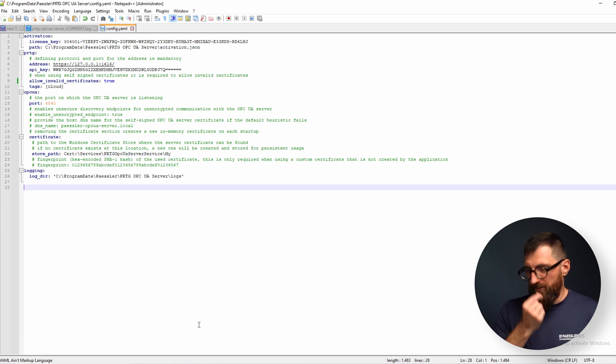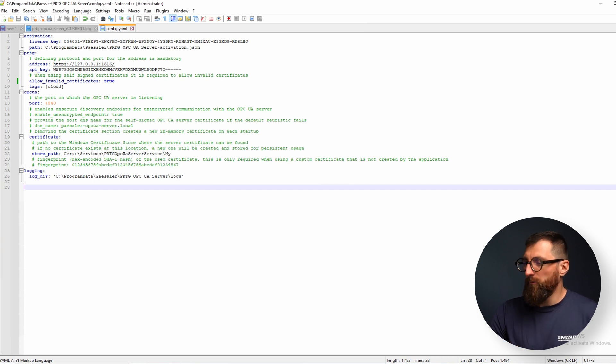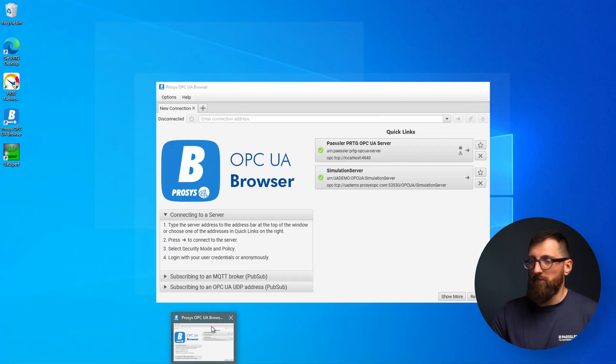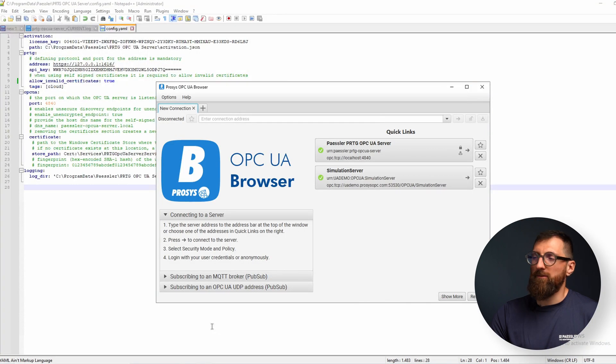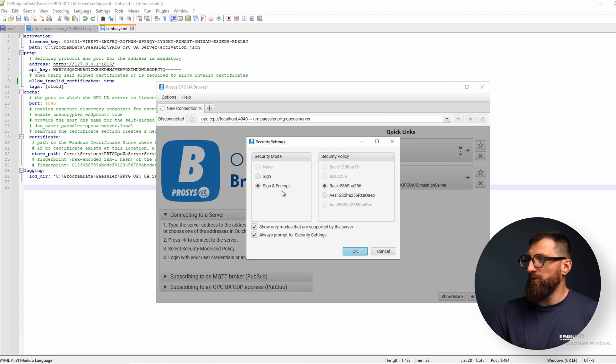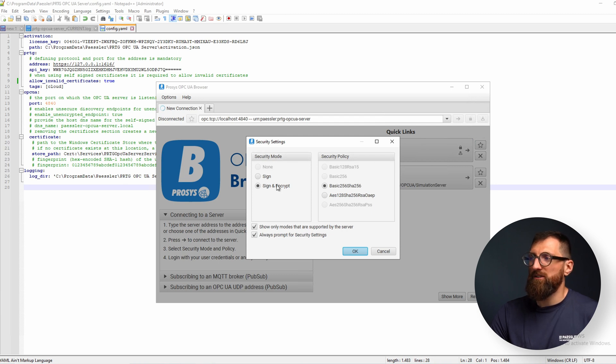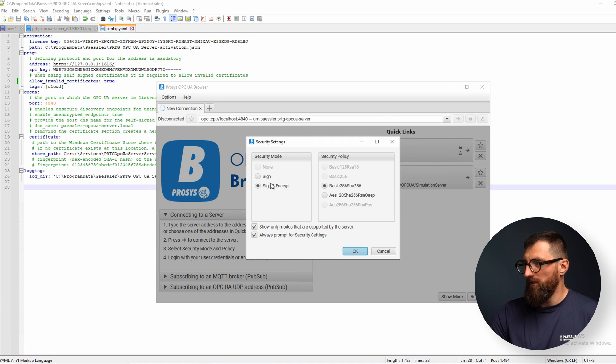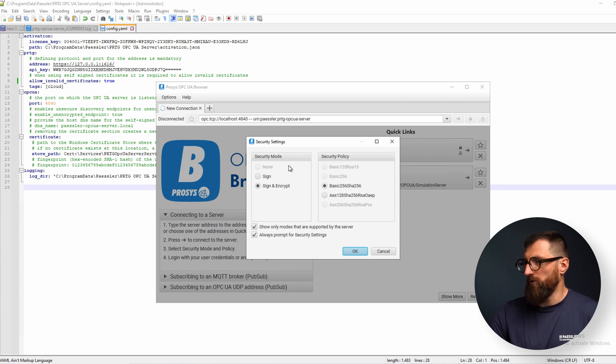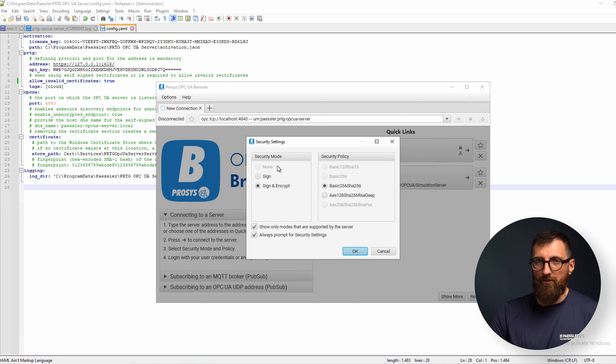To be sure that our data is exposed via OPC UA we can open any OPC UA client. In my case I use the Prosys UA browser and connect on localhost. As a default we only support security mode sign and sign and encrypt. If you need the none security mode because your device does not support any security or encryption, you can also enable this in the configuration file.